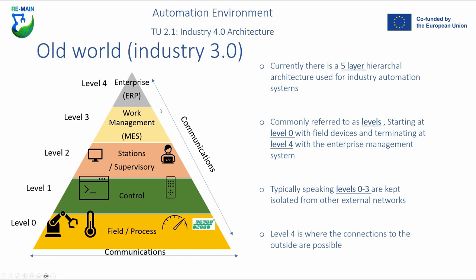The levels are typically kept isolated from other external networks as much as possible, to minimize risk from intrusion or cyber attack and to ensure that the manufacturing process is robust and not compromised. If you do need to connect to the outside world, that generally happens at level four. Communications can go from level to level — level zero to one, one to two, two to three, and three to four — and vice versa. Communications can also occur on the horizontal axis, so anything within level zero can potentially communicate with anything else within level zero.